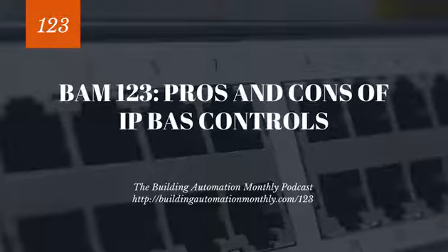Now the cons are, now you have moved into a power dependency. At least at the time of this recording, the majority of the manufacturers out there have a power dependency on their network interface cards. What that means is on that actual controller, you have those network interface cards that the Ethernet ports are attached to. In order for that controller to process the message, to process that Ethernet frame and that IP packet, and then forward it out the next port, you need to have power to those network interface cards. With BACnet MSTP, you could get away with a lot, because if you didn't have power at that controller, the wire itself was powered and it would just continue along.